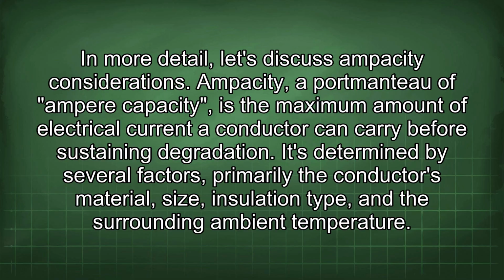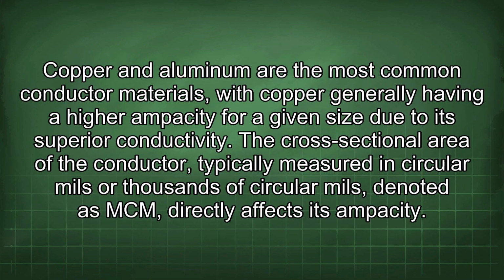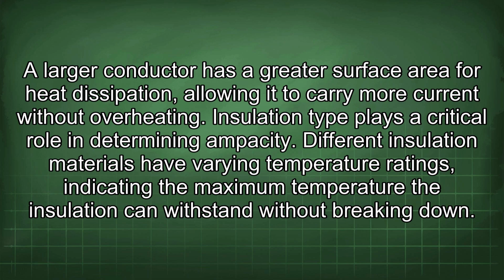It's determined by several factors, primarily the conductor's material, size, insulation type, and the surrounding ambient temperature. Copper and aluminum are the most common conductor materials, with copper generally having a higher ampacity for a given size due to its superior conductivity. The cross-sectional area of the conductor, typically measured in circular mils or thousands of circular mils, denoted as MCM, directly affects its ampacity. A larger conductor has a greater surface area for heat dissipation, allowing it to carry more current without overheating. Insulation type plays a critical role in determining ampacity.